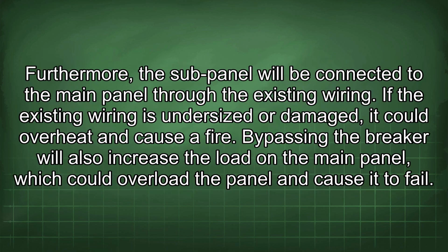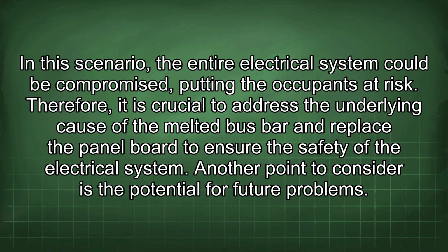Furthermore, the sub-panel will be connected to the main panel through the existing wiring. If the existing wiring is undersized or damaged, it could overheat and cause a fire. Bypassing the breaker will also increase the load on the main panel, which could overload the panel and cause it to fail. In this scenario, the entire electrical system could be compromised, putting the occupants at risk. Therefore, it is crucial to address the underlying cause of the melted bus bar and replace the panel board to ensure the safety of the electrical system.